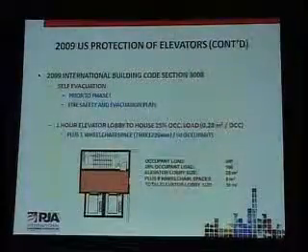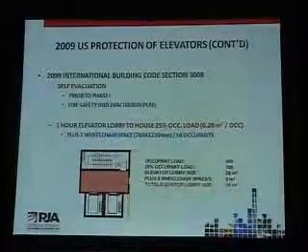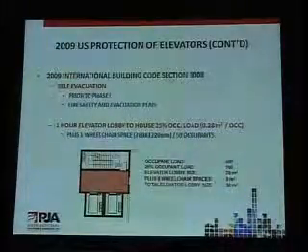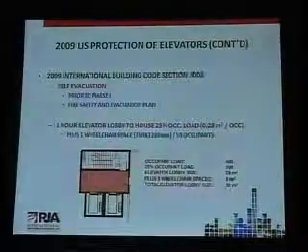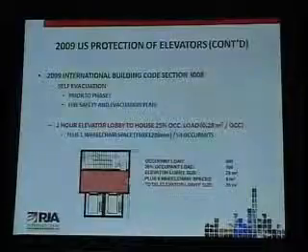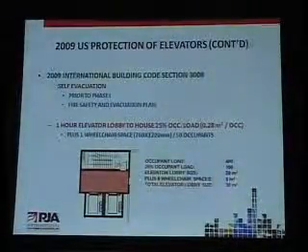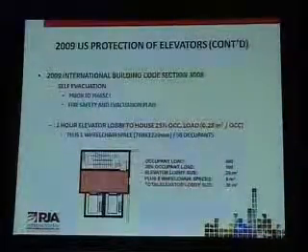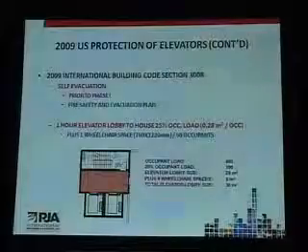Now, I want to go back to this quick slide. If you're going through this in your head on evacuating a building that has this feature, obviously to get to the stair and to get to any exit, you're going to have to go into this vestibule. You wait for the elevators to be called, and the sign's green, so you can wait. Sign turns red. Well, when the sign turns red, you can identify that you can no longer use the lifts, and you have direct access into the stair, so you no longer have to go back into the fire zone.